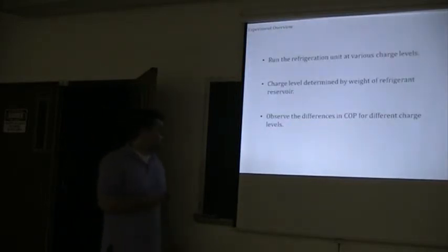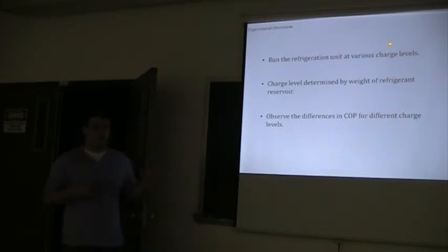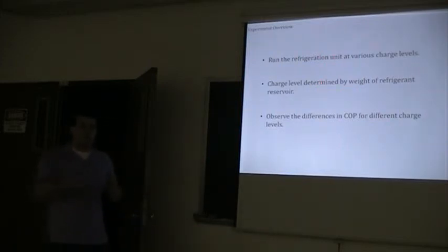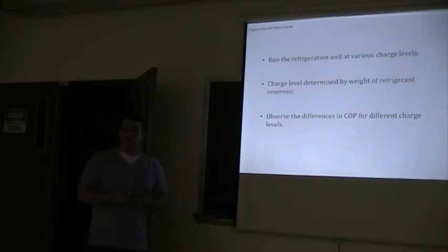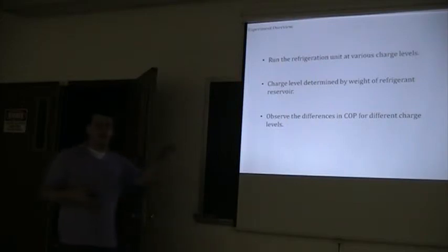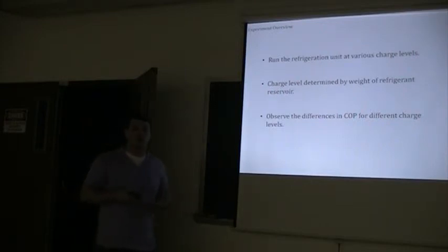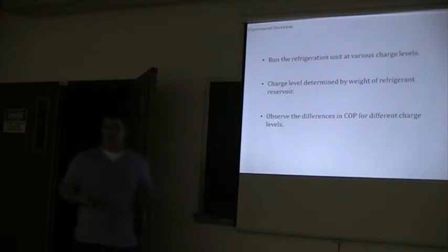All right, so like I said earlier, we're going to run the refrigeration unit at various charge levels. And the way it's determined how much charge you have in the system is by weighing the reservoir. As you increase the amount of charge on the system, the weight of the reservoir is going to decrease.